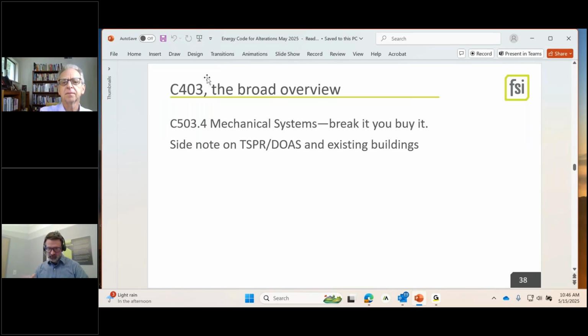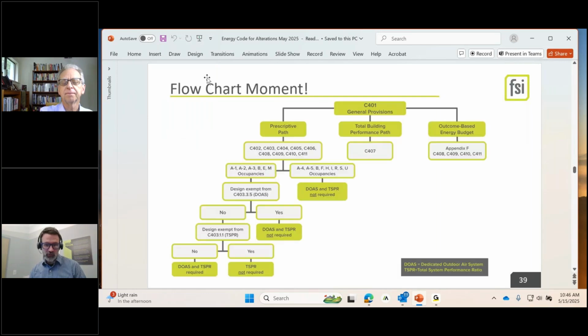C403, right at the top of the section, has the total system performance ratio that Duane already mentioned, and some dedicated outside air with energy recovery. Yeah, there's the engineer, or the engineer by way of marketing, version of a flow chart. So you've also got energy recovery ventilation requirements or some exceptions. It's a rather long list for both of those. But if your specific occupancies trigger TSPR, it's its path.